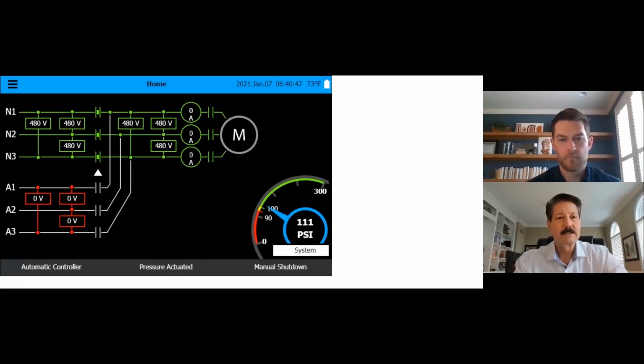It's quite nice. Looking at this immediately, it's like driving in the United States or anywhere in the world. In most cases, if you have a stoplight, green is on or go, energized, yellow is caution or transition, and red is stop or off. The same thing applies here. Looking at the specific diagram, we have power all the way through to the line side of the contactor. The contactor's open, the motor is gray, it's off.